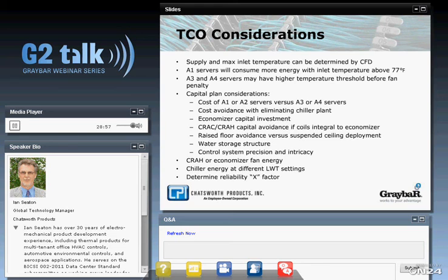And to put it in perspective, depending on how many servers you have in a data center, a 1% decrease in reliability may result in one more server every 5 or 10 years that would require a reliability-based replacement. So those are just factors that need to be included into the overall budget.